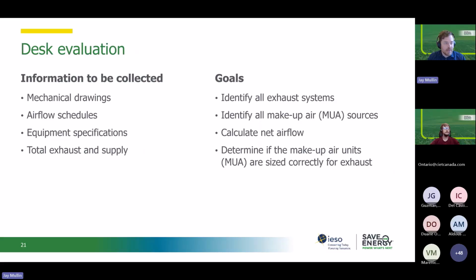The desk evaluation is really about collecting information, records, and information about equipment. For exhaust systems, you're looking at the process exhaust, dust collectors, fume hoods, general exhaust, bathrooms, boiler, or other combustion equipment. And for makeup air, you're looking at dedicated makeup air units, outdoor air dampers on air handling units, door louvers, and infiltration through the envelope. You're going to be collecting mechanical drawings, airflow schedules, equipment specifications, finding out total exhaust and supply capabilities and ratings.